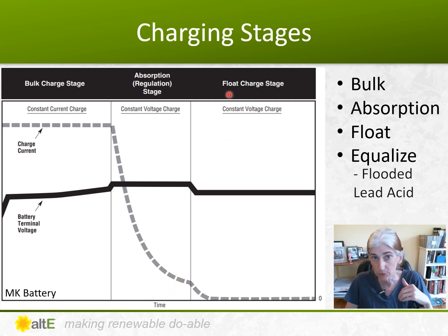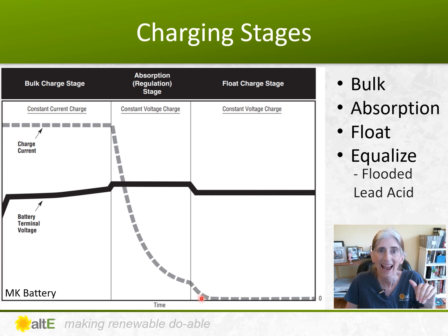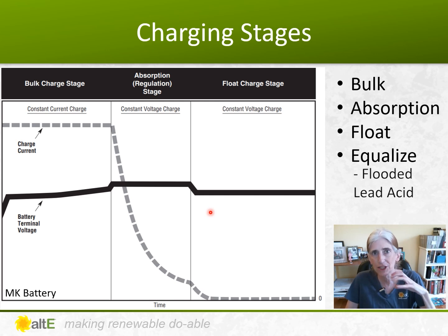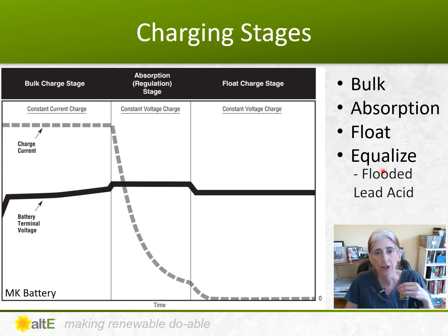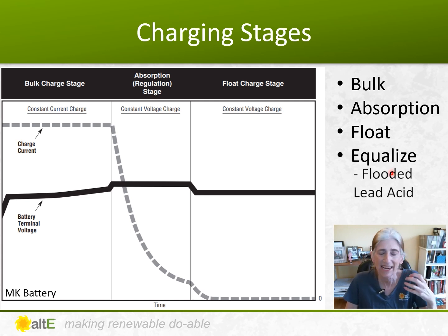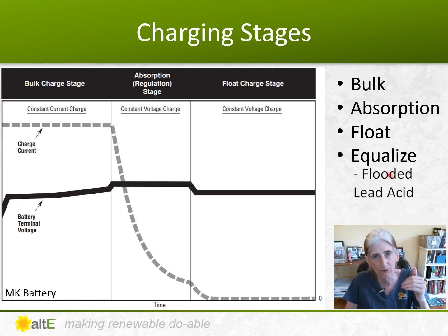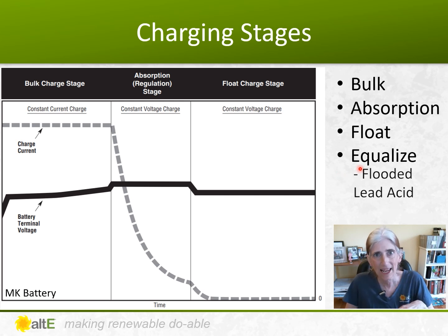The next stage is float. At float, your voltage drops back down to around the full battery voltage, and your current is pretty much down to zero because the battery is full and you're just keeping it topped off. If you have a flooded lead acid battery, you'll also talk about equalizing it — maybe once a month, you throw a really high voltage at it. That shakes off any sulfation that's formed on the plates and makes sure each individual cell is fully charged, getting the whole battery healthy and full. You only do this with flooded lead acid batteries, not with lithium or sealed batteries.